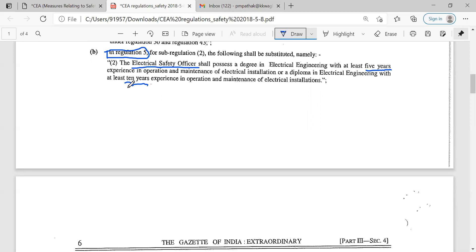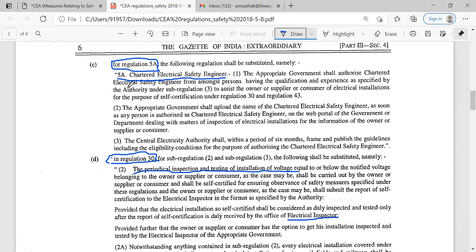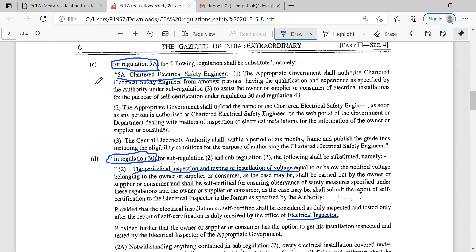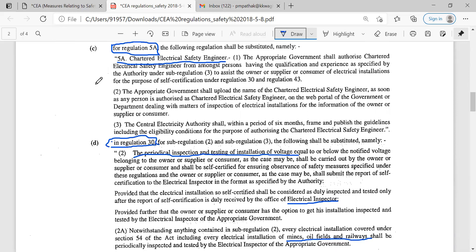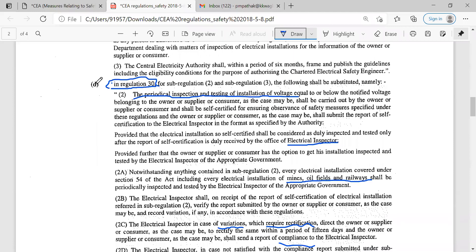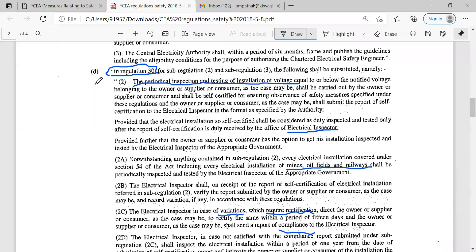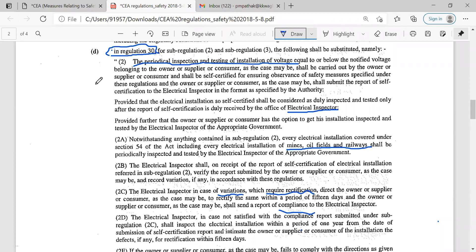In regulation 5A, that is chartered electrical safety engineer, with reference to rule number 30 and 43, this is approved by or designated by the appropriate government with reference to rule numbers 30 and 43. Regulation 30, that is periodic inspection and testing of installations and voltage — that is the main focus of this change. The electrical inspector is responsible for this inspection, or the periodical inspection and testing of this installation of voltage equal to or below the notified voltage.